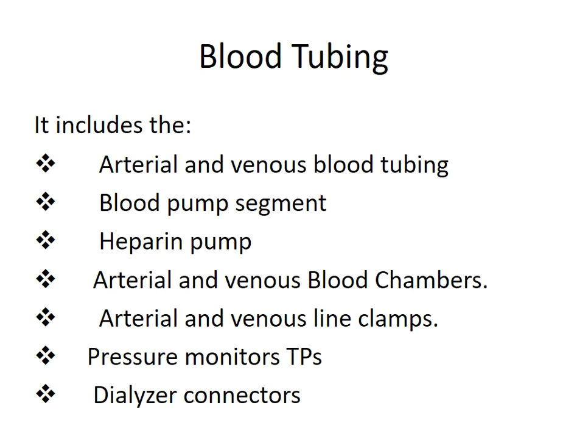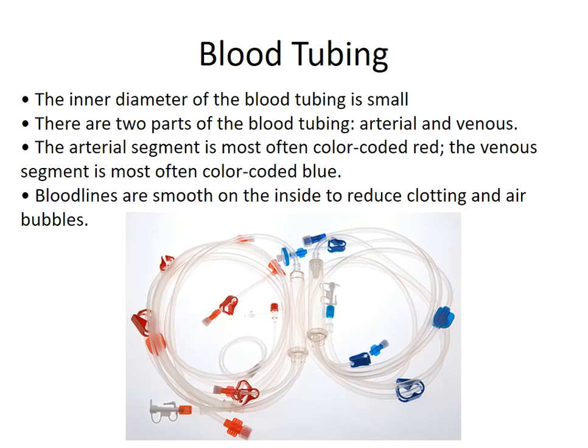The blood tubing includes the arterial and venous blood tubing segments, the blood pump segment, heparin pump, arterial and venous blood chambers, arterial and venous line clamps, pressure monitors, transducer protectors, and dialyzer connectors. The arterial segment is color-coded red and the venous segment is color-coded blue. The inner diameter of the blood tubing is small. The blood line should be smooth on the inside to reduce clotting and air bubbles.